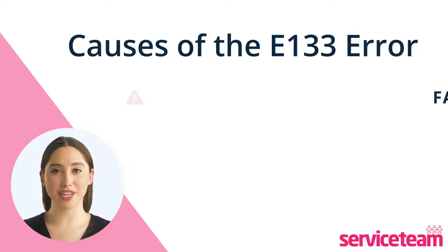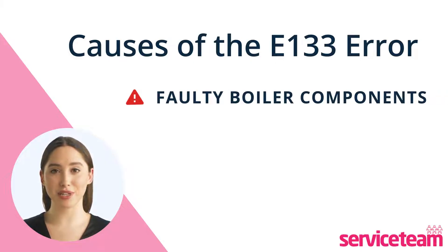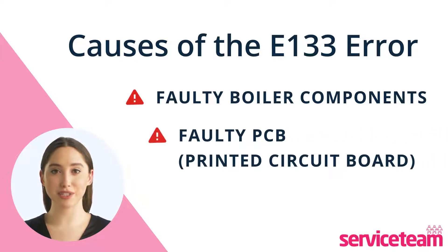The next reason could be a broken or faulty component in the boiler. If there's a faulty component, it should be replaced. Gas supply issues are often linked to defective boiler parts. A broken printed circuit board can also lead to the E-133 boiler fault. If there's no continuous connection in the cable between the control panel and the burner, it might be a problem.